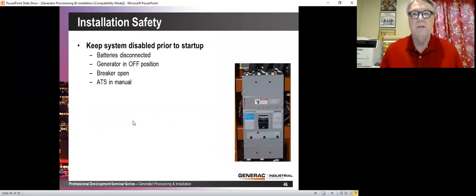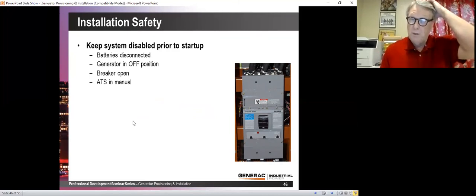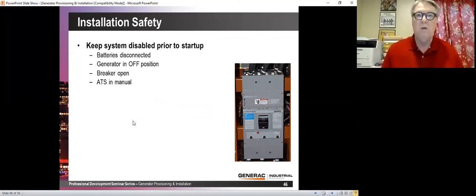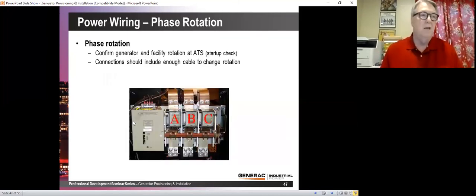Keep the system disabled prior to startup. If you connect the batteries, they are going to turn on the controller, and in about 24 hours, that controller is going to discharge the batteries, and then you will damage the batteries. So keep them disconnected until you hook up your control power to the battery charger. Generator in the off position, breaker open, ATS in manual, and the startup person will take care of that.